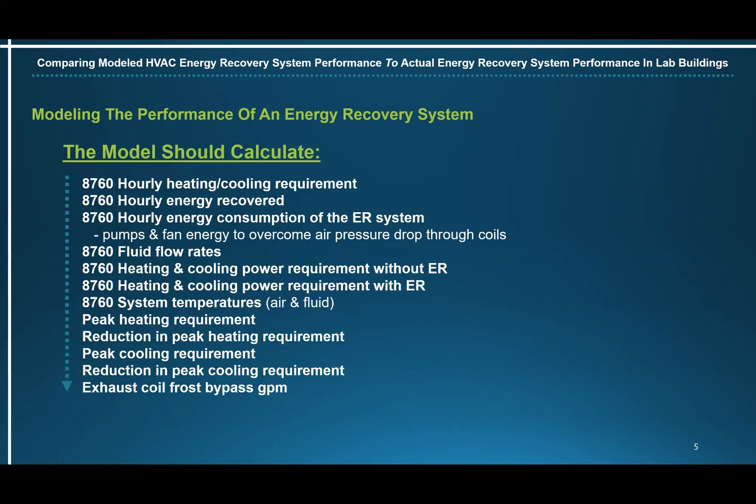The model should calculate: 8760 hourly heating and cooling requirements, 8760 hourly energy recovered, 8760 hourly energy consumption of the energy recovery system, 8760 fluid flow rates, 8760 heating and cooling power requirements, 8760 power requirement without energy recovery, 8760 system temperatures both air and fluid, the peak heating requirement, the reduction in peak heating requirement, the peak cooling requirement, the reduction in peak cooling requirement, and exhaust coil frost bypass GPMs.